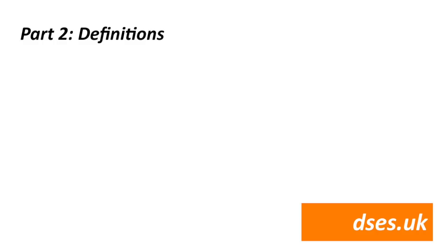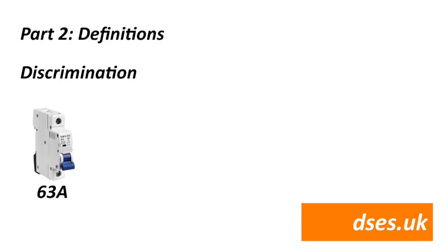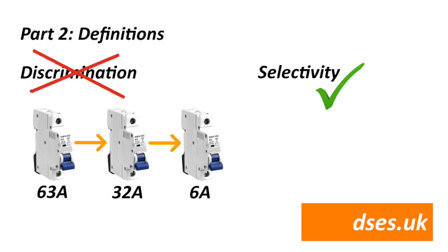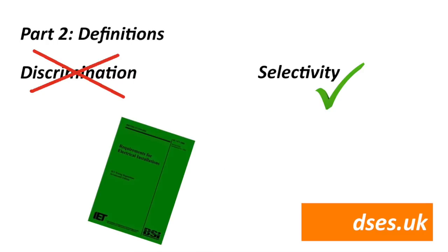We start at Part 2, where there are various changes in the definitions. One of the more obvious is the term 'discrimination' — which basically meant that further downstream on a circuit, the lower the value of the localised protective devices. That term has been replaced by the more positive-sounding 'selectivity'. To be fair, selectivity has been in the definitions list for some time — certainly in the green book of 17th edition incorporating Amendment 1 from 2011 — but previously it simply referred you back to discrimination. Now discrimination is gone entirely, its definition encompassed under selectivity.